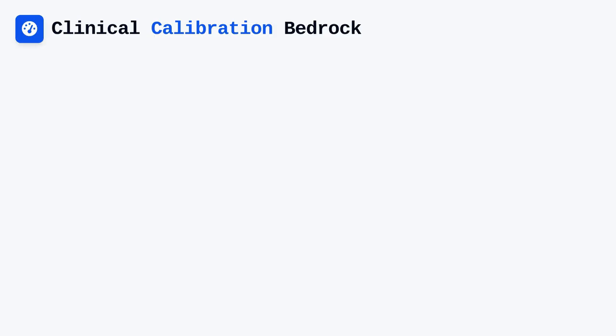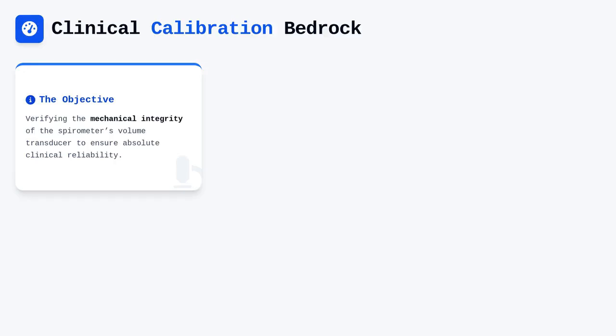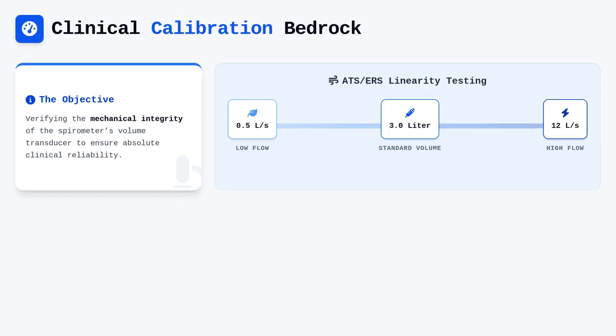When we speak of daily volume calibration using a 3-liter syringe, we are verifying the mechanical integrity of the spirometer's volume transducer. The ATS/ERS guidelines explicitly demand that we inject the 3-liter volume at varying speeds, typically ranging from 0.5 to 12 liters per second, to assess the linearity of the device across the entire physiological spectrum. If a device fails to accurately measure the volume at low or high flows, it suggests a mechanical obstruction or a calibration drift that must be rectified before patient testing proceeds.